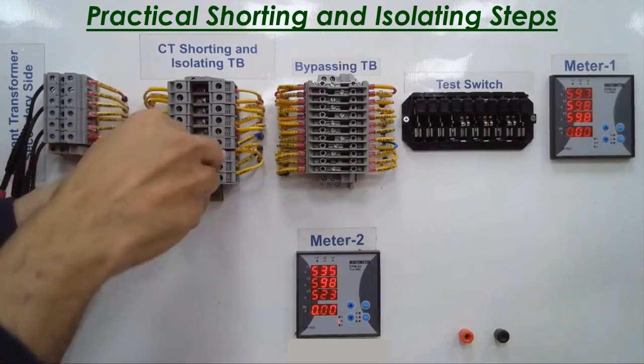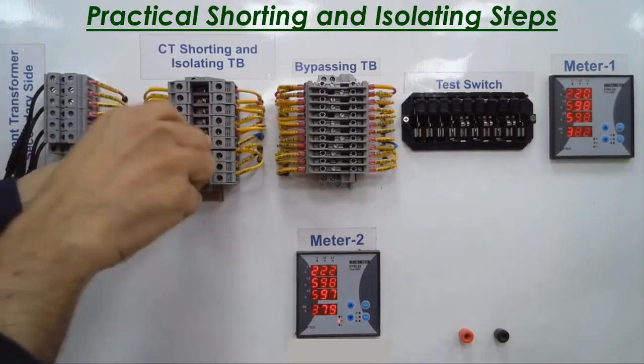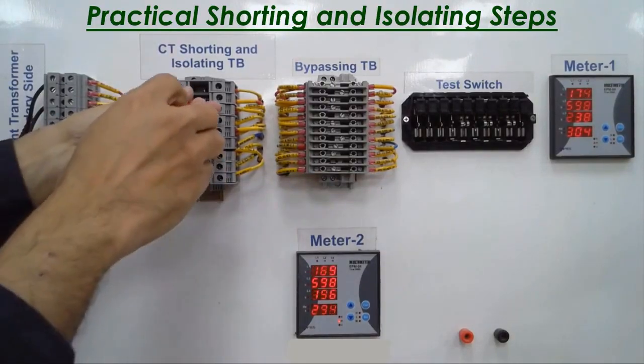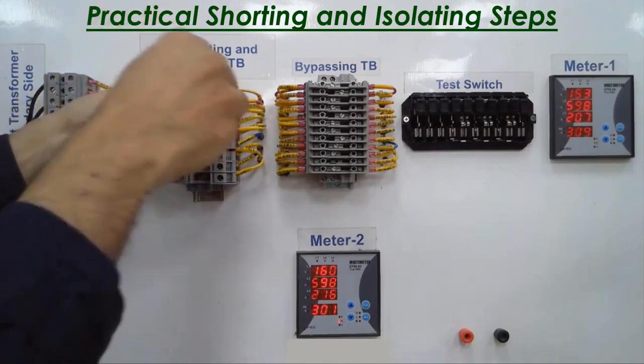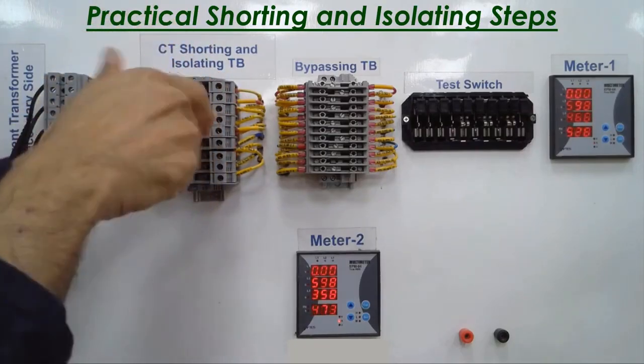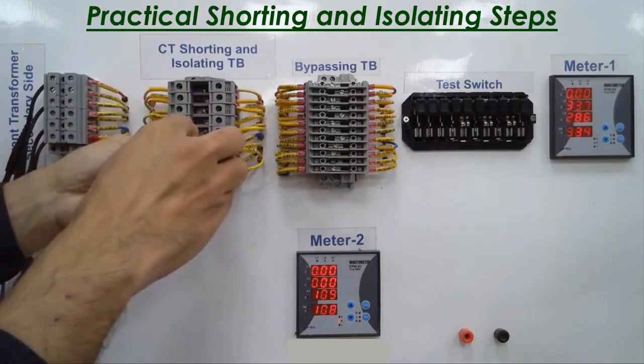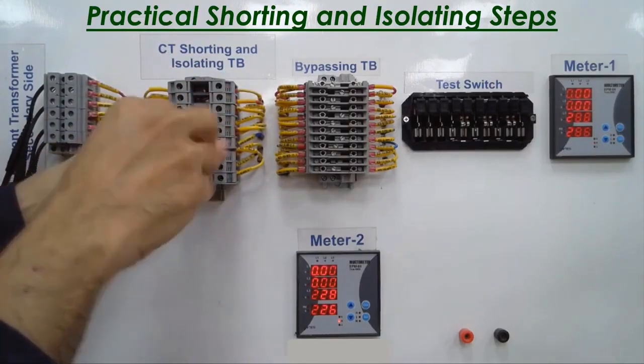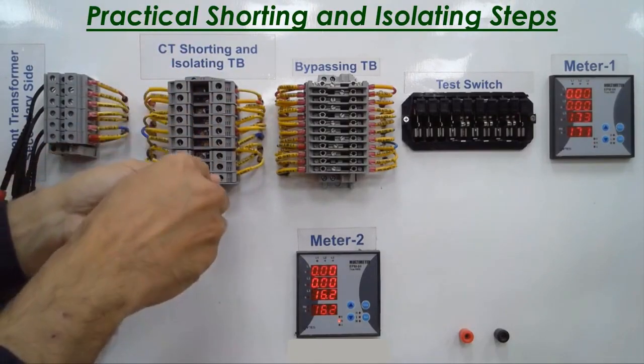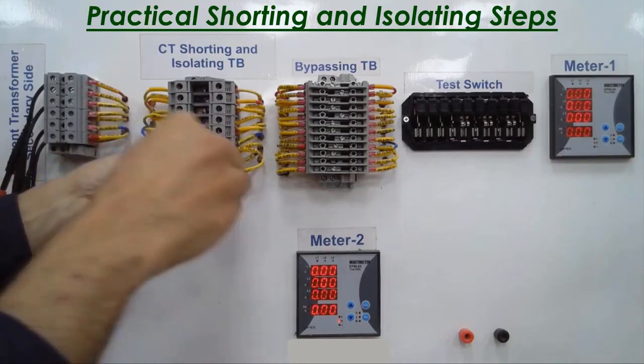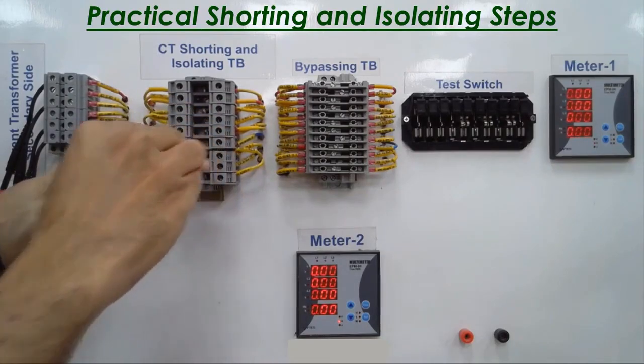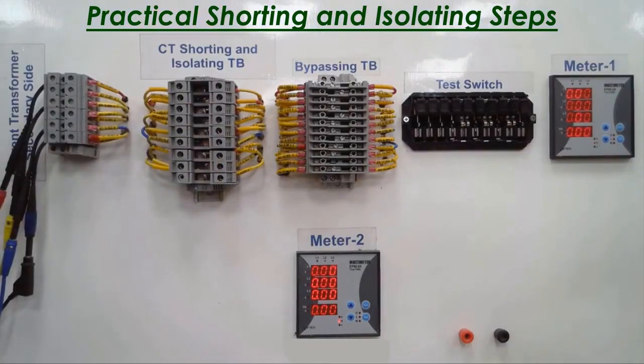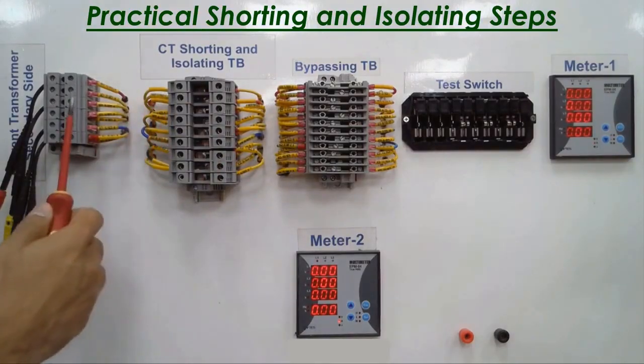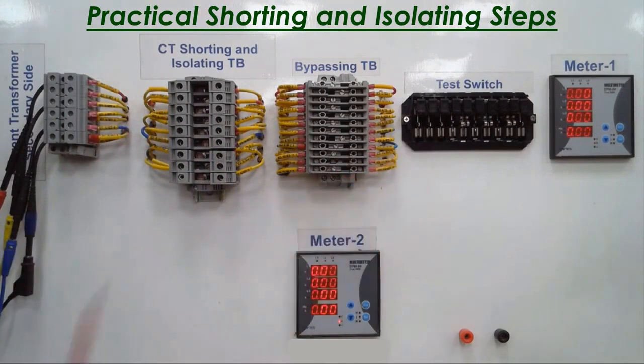Then here is terminal number 7. As you can see, very good. After that, I start opening terminal number 2, and then terminal number 4, then terminal number 6, and terminal number 8. In this way, of course, we saw that I did a shorting on the CT circuit and isolated the power meters from the secondary circuit of the CT.